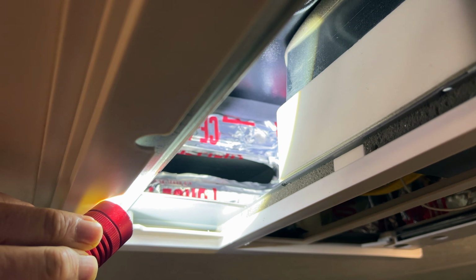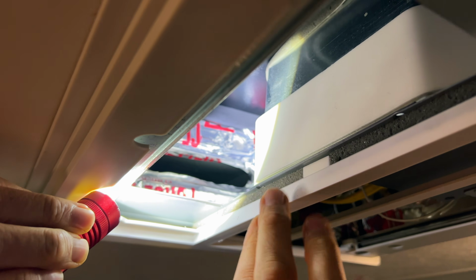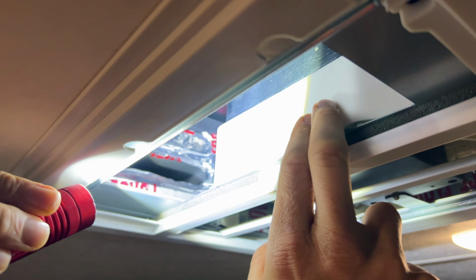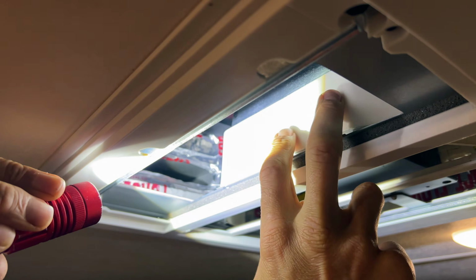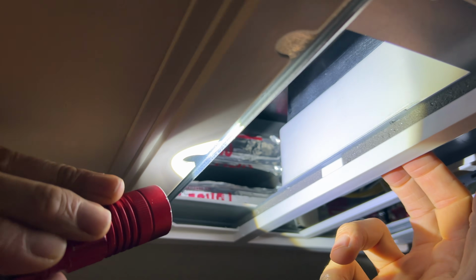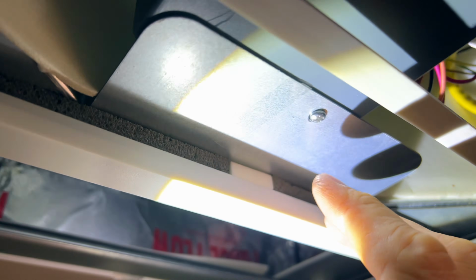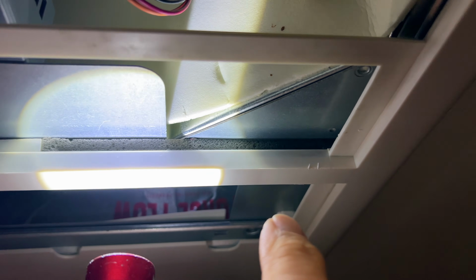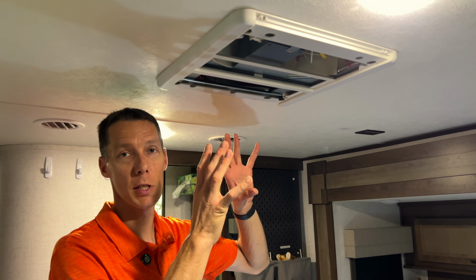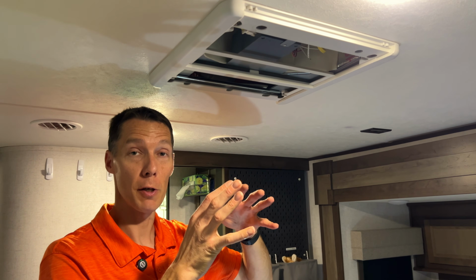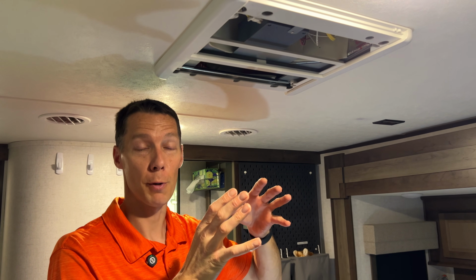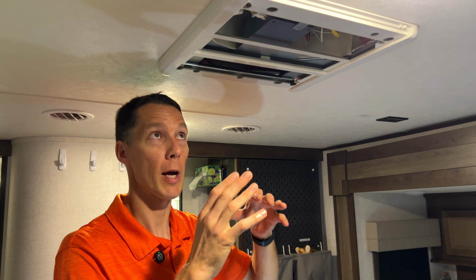And this is the back side of your plenum divider. So this is nice and smooth and sealed off well. If there were gaps in this, like you saw gaps in the other side, you can seal up either side with foil tape to make sure air is not leaking between one side and the other. And while you're around the control box in this part of the AC unit, if you want to use a multimeter, you can check the amp draw of the compressor. The wire you would check is coming out of the control box.